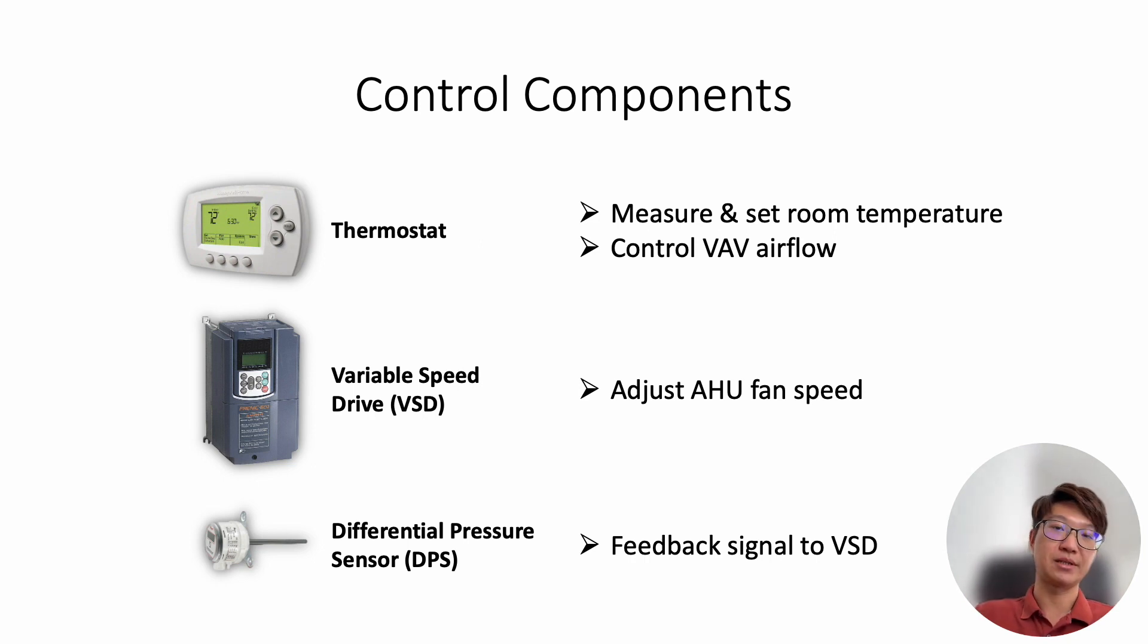Then the third component we need to control the VAV system is the differential pressure sensor, DPS. This is the duct type differential pressure sensor. It will be installed inside the duct. So because when the VAV starts to close, it will increase the air pressure inside the duct. So this sensor will pick up the signal and tell the VSD to reduce AHU fan speed.